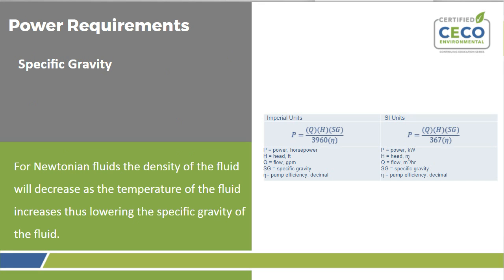The first is power requirements, and this goes back to the changing properties of the fluid itself. For Newtonian fluids, the density of the fluid will decrease as the temperature of the fluid increases. It lowers the specific gravity of the fluid. As you can see, in the equation on the right, the power required on a centrifugal pump is the flow rate times the amount of head times the specific gravity over the efficiency of the pump itself. Because the specific gravity is in this equation, that means that the power required for this pump will change as the density of the fluid changes. So that means that it will change as the temperature of that fluid changes.